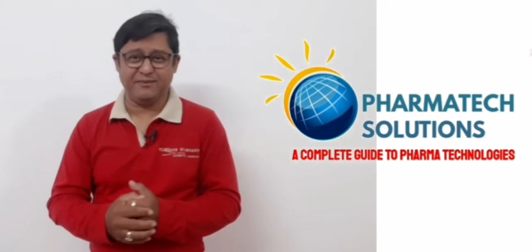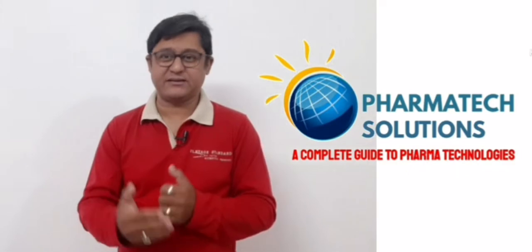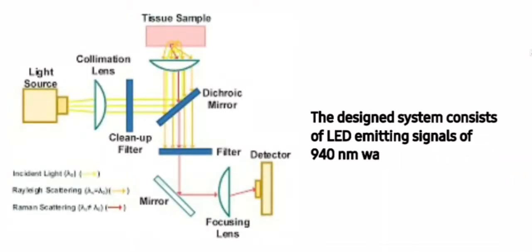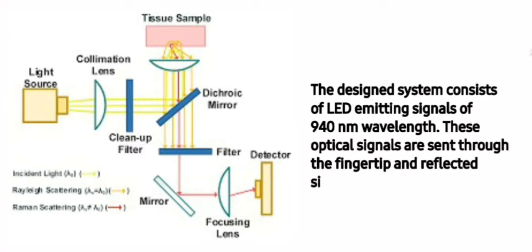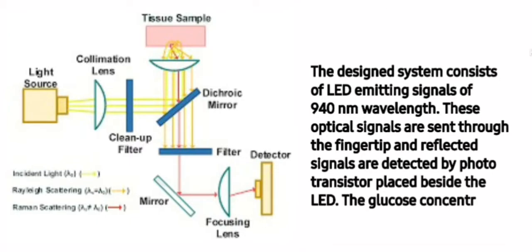Sounds a little confusing? Let me explain it in a simple way. The designed instrument consists of an LED emitting signals around 940 nanometer wavelength, and these optical signals are sent through the fingertips.